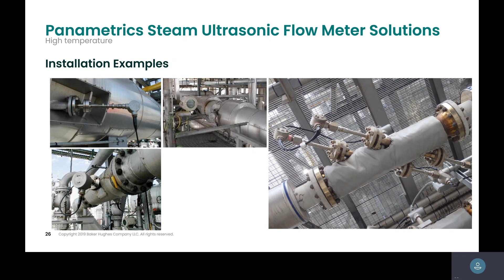I always use the analogy that apples are not the same as oranges. So when we go out to work on any type of steam measurement, we don't just ask, hey, what's your flow rate? We ask for temperature, pressure, pipe condition, flange class, and what your overall expectations are for the measurement - just to get a better understanding.